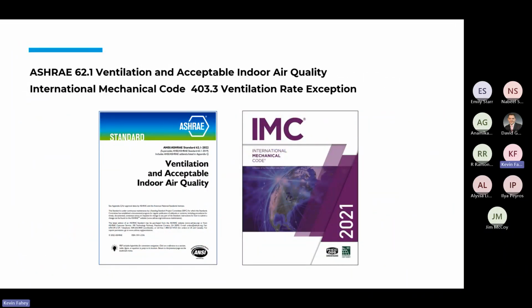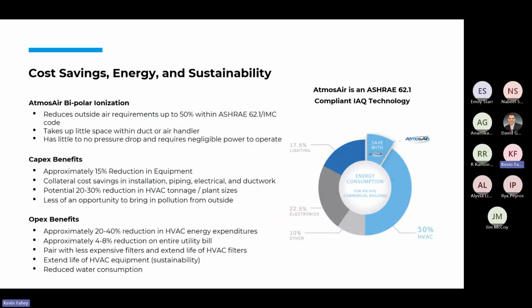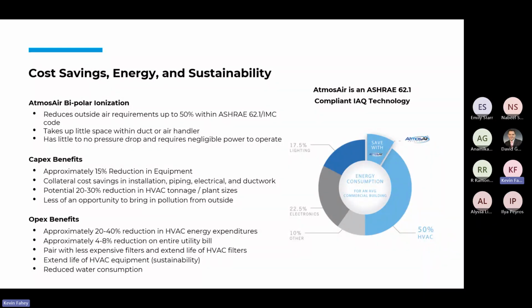We mentioned earlier using ASHRAE's 62.1 indoor air quality procedure or the IMC, the International Mechanical Code. Both of those allow you to provide an engineered approach to outdoor ventilation versus using the ventilation rate procedure. If you do use 62.1, with our technology we have certain testing that allows it to be used, and you can usually reduce your outdoor ventilation 50% from what it would be with the ventilation rate procedure. If you do that, you can get a reduction in the tonnage of heating and cooling that you're going to require, and save money on first cost. You can also reduce your ongoing expenditure because you're going to be conditioning less outside air.